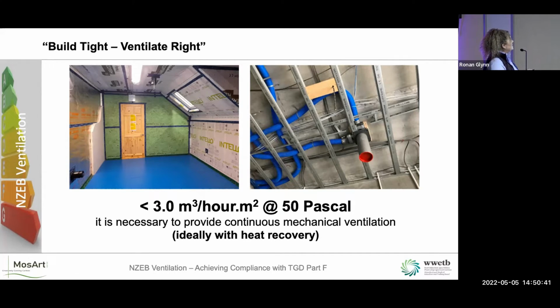That blue Tescon Vana tape is actually accelerated age tested in the Kassel University, and that's supposed to last 100 years. So whatever tapes and membranes you put in, you need them to last the lifetime of your building. So below 3 meters cubed per hour per meter squared at 50 Pascal, we have to provide mechanical ventilation, ideally with heat recovery. So if you see the example on the right hand side, now you have to think about dropped ceilings, where are you going to put your ductwork? We don't want to put it up in the attic. So we'll have a look further at that.